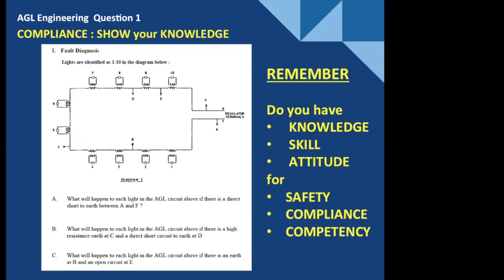What will happen to each light in the AGL circuit if there's a direct short to earth between A and F? Current will leave the CCR, go to earth, come back in, and return to the CCR. All those lights will go out.